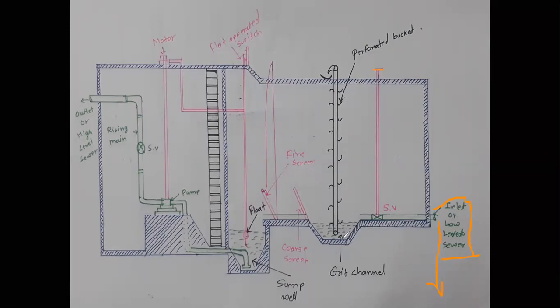After that sluice valve, the sewage will enter this grit channel. What is meant by a grit channel? Where the grit particles can be removed. What are the grit particles? Debris particles, sand particles, crushed stones, egg shells, or whatever inorganic material in a small, settleable form can be identified as grit. Here a hopper bottom tank has been constructed to settle out the grit particles. These are sedimentary, heavy particles, so they will settle in this portion.